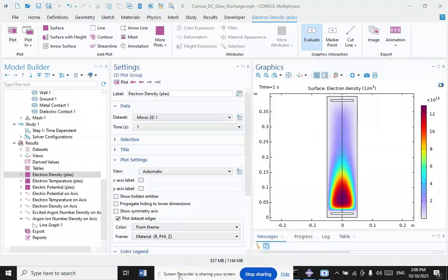Energy gained through collisions can also ionize the sample atoms. The ions can then be detected by mass spectrometry. In this case, it is the mass of the ion that identifies the element and the number of ions that reflects the concentration. This method is referred to as glow discharge mass spectrometry, or GDMS, and it has detection limits down to the sub-ppb range for most elements that are nearly matrix independent.